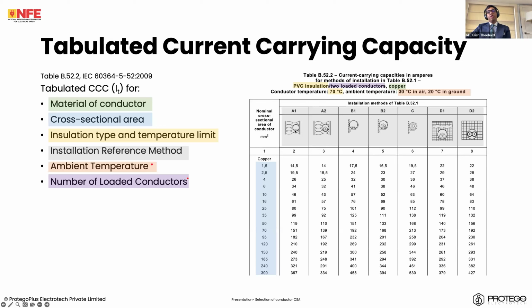What is the installation reference method? So A1, A2, B1, B2, C, D1, D2. The ambient temperature, so 30 degrees in air, 20 degrees in ground. And the number of loaded conductors, two loaded conductors. The idea really, again, is to make sure that we come up with the right tabulated current carrying capacity, and looking at the right table as well.